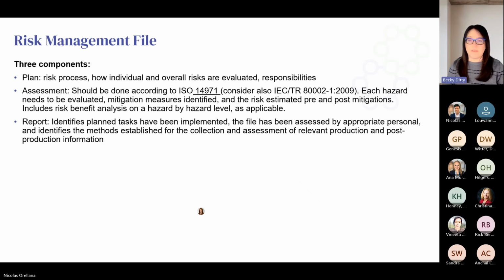You'll also have a risk management file, and this will be in accordance with 14971. You'll have three parts to that risk management file. You'll have the plan that identifies who needs to be involved in the risk management process, and how are you evaluating risks on an individual level and as a whole for the device to determine whether or not they're acceptable. Additionally, you'll have an assessment that goes through for each hazardous situation and evaluates it, gives it a score pre-mitigation, and then identifies what are the causes of it. What mitigation measures do you put in place to prevent that from happening? And then after those mitigations, what is the risk level at that point?